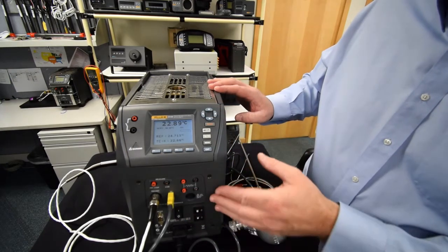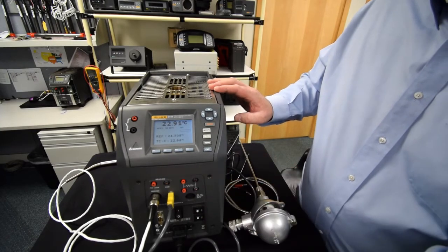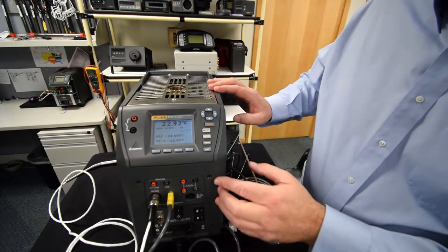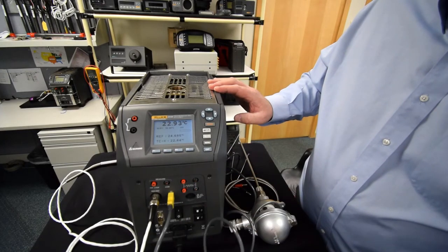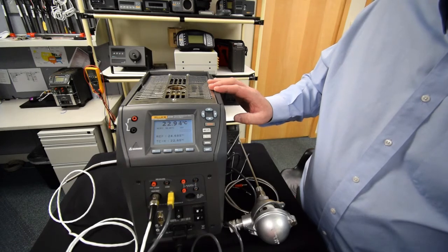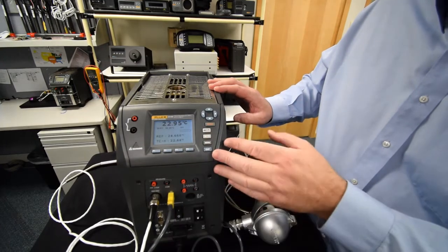we also have the unit with the process option that allows for an external reference probe, as well as options for devices under test. And in this example, I've got a type K thermocouple also connected to show you the display how it breaks it out.